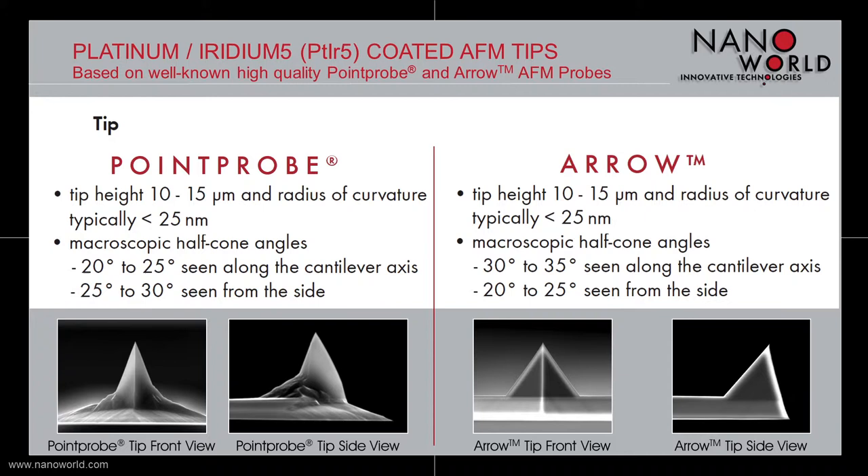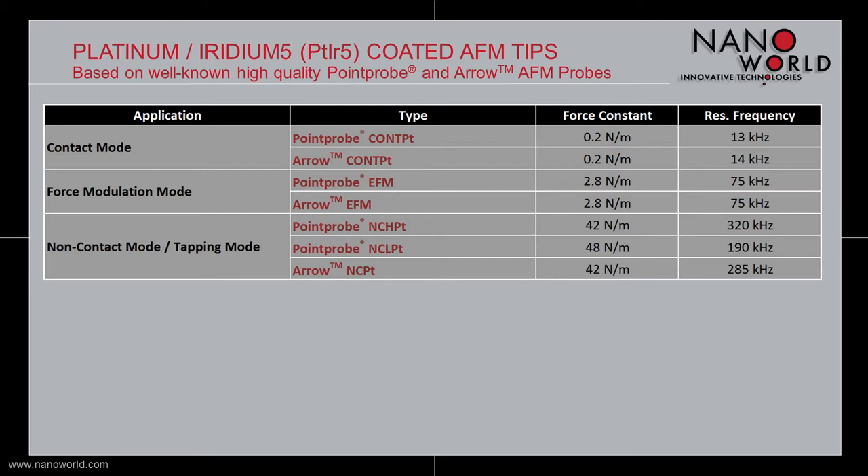The arrow based Platinum Iridium 5 tip is also 10 to 15 micrometers high and has a typical radius of smaller than 25 nanometers. The macroscopic half cone angles are 30 to 35 degrees when viewed along the cantilever axis and 20 to 25 degrees viewed from the side.